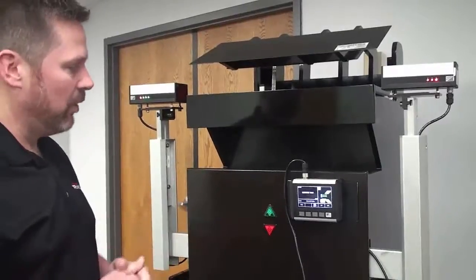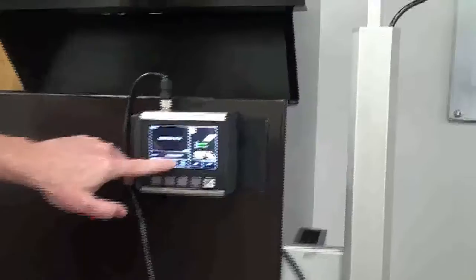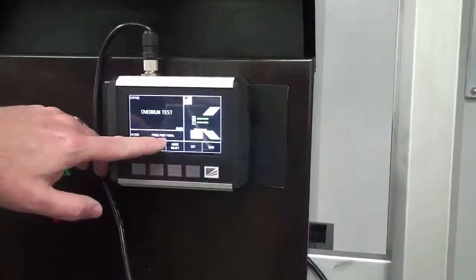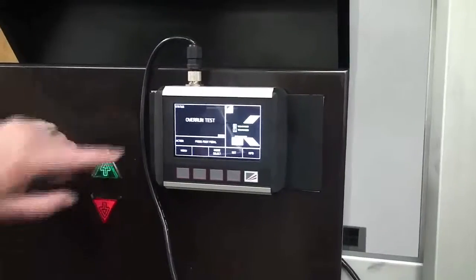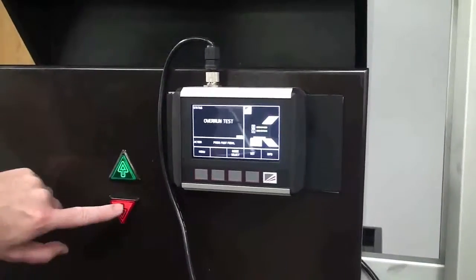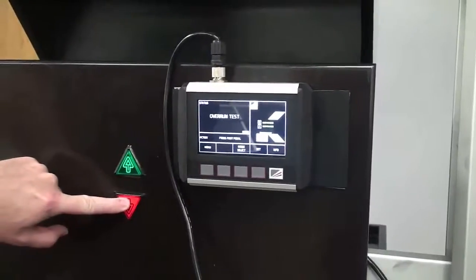It's going to tell me to run an overrun test. I see an action. The action is telling me to push and press the foot pedal. Now, these buttons are going to simulate my foot pedals. So the first thing I want to do is I want to do a foot pedal press. If we watch the clamp, it's going to lower, and it's going to stop.